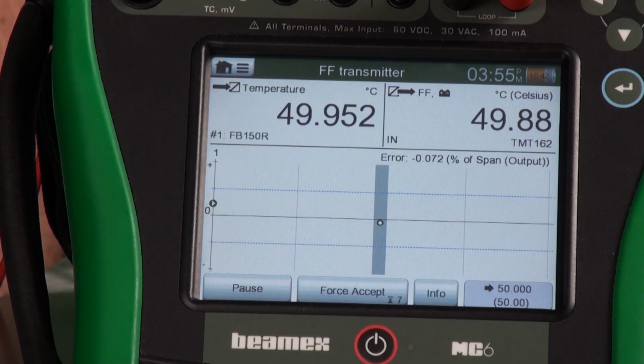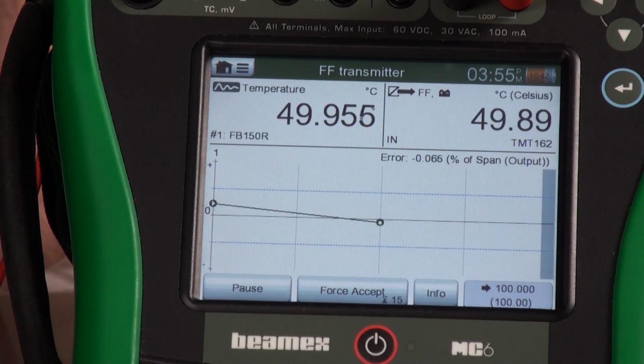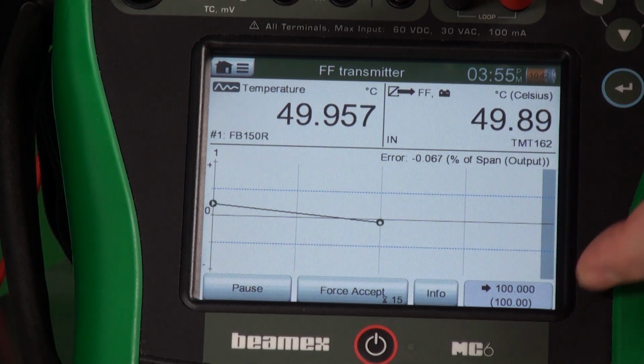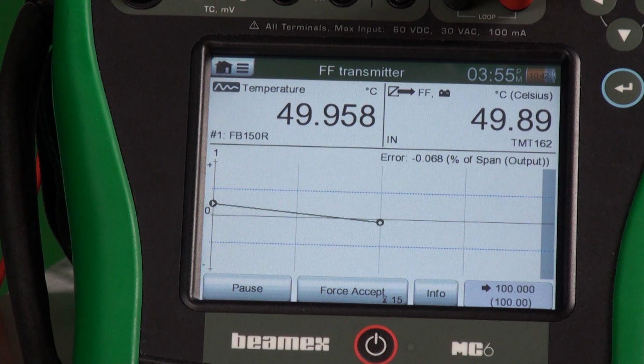We've reached our second test point of 50 degrees. The calibrator will grab that test data and tell the dry block to move on to the next test point. You can see here on the bottom right, that tells us where the calibrator is going. So it's pushing us towards 100 degrees C, and it also says that we're expecting 100 degrees on the output as well.